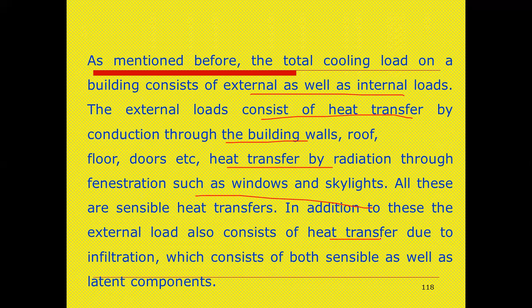All these are sensible heat transfers. In addition, external load also consists of heat transfer due to infiltration, which consists of both sensible as well as latent components. The heat transfer due to ventilation is not a load on the building but a load on the system. The various internal loads consist of sensible and latent heat due to the occupants, products or processes, appliances, and sensible heat transfer due to the lighting and other equipment.